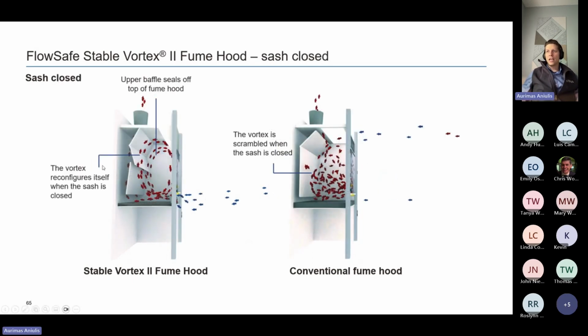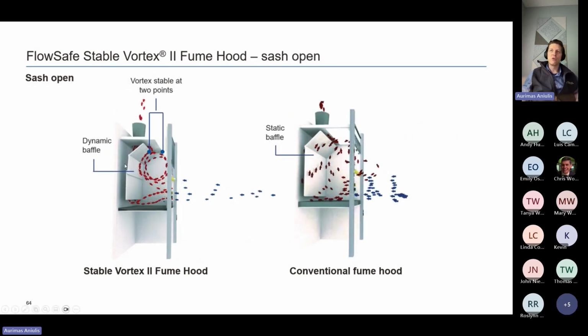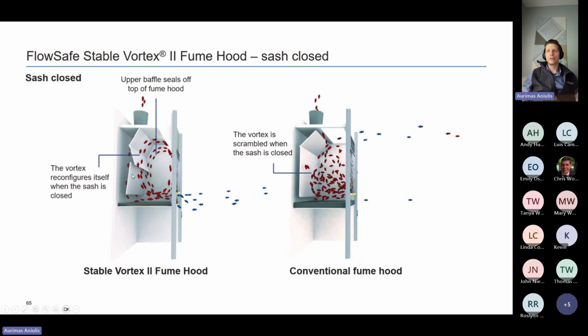Again, showing a little bit, when the sash is closed, that vortex does descend and touch the work surface of the fume hood. It does expand across the workspace. And as you lift the sash, it does rise up and become smaller in area. These are fairly evident in smoke tests. If you ever see one in person, as you raise and lower the sash, that vortex tracks the fume hood sash opening. And the advantage here is that I can get the same levels of safety at 60 feet per minute versus 100 feet per minute.